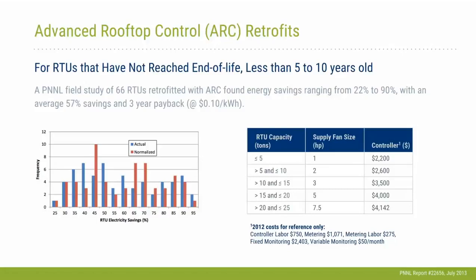We've done an exhaustive field test of these units. We typically found that larger units, maybe greater than 5 tons, that run for longer periods—10 hours or more a day—typically have paybacks of less than 3 years. The cost information shown here is from a report we did about 5 years ago, so it's a bit dated, and the costs are probably lower than what's shown in this slide. That's something to be aware of.